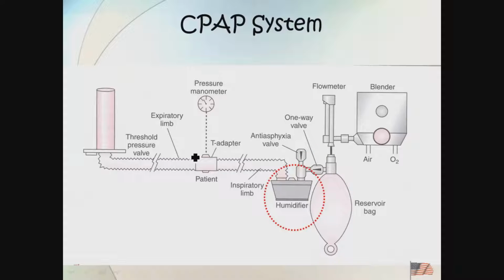Humidifier. Dry gas out of the wall is not pleasant, especially at higher flows. An anti-asphyxia valve. An anti-asphyxia valve says if this flow meter should come loose, that means there's no flow going to the bag, there's no flow going to the humidifier. Ooh, that could be bad for baby. So I have a one-way valve there that allows them to breathe through the atmosphere. Because this is a closed system.